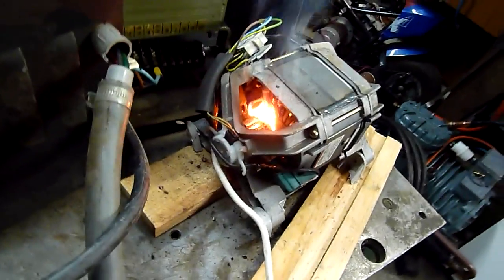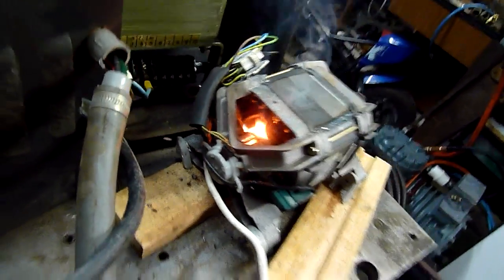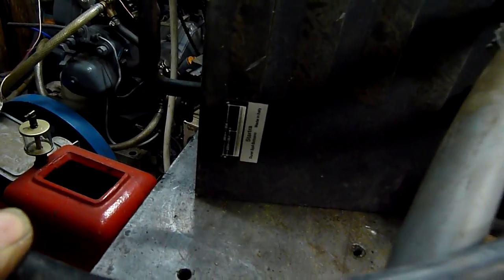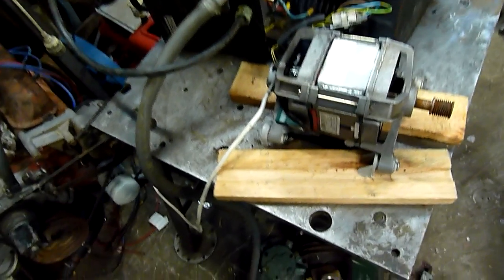I'm not talking critical speed, it's just pure amperage. Like wow, it's taken out the air conditioning circuit breaker, but that's only 20 amps. So what's it rated for? Yeah, 380 volt, 20 amps on the secondary. God knows what the primary current was - I guess I should put a meter on it.